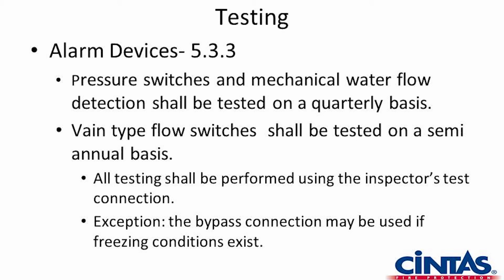Again, talking about testing, pressure switches and mechanical water flow detection shall be tested on a quarterly basis. A pressure switch is the same thing as a water flow switch, but a pressure switch would be installed on a dry system. On a dry system, we're not allowed to put the vane type, where we fold the disc over and slide it through a hole cut in the pipe when the system is installed. It lays in there and waits for the water to flow so it raises up.